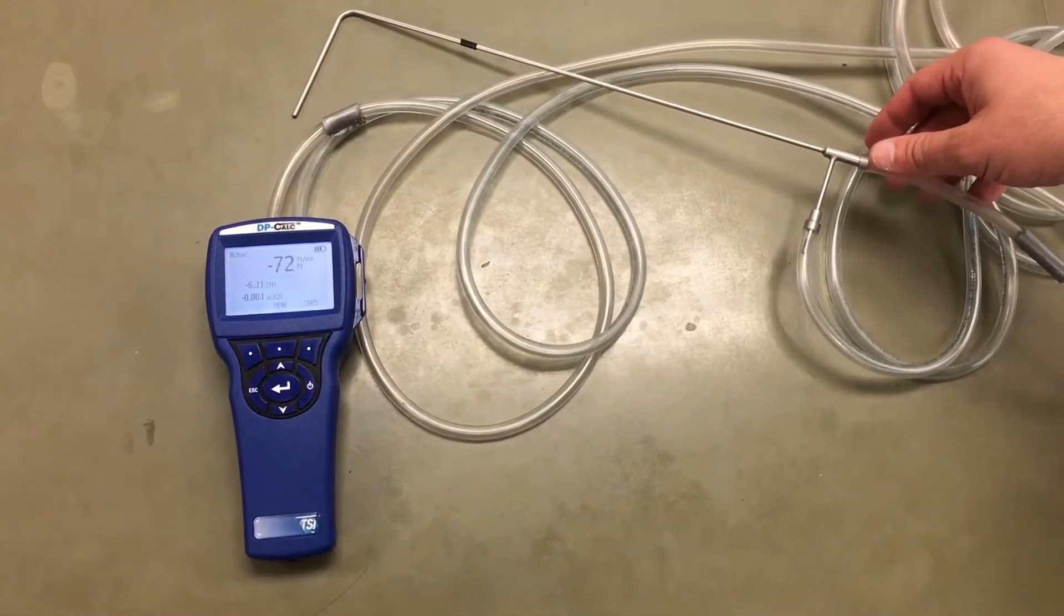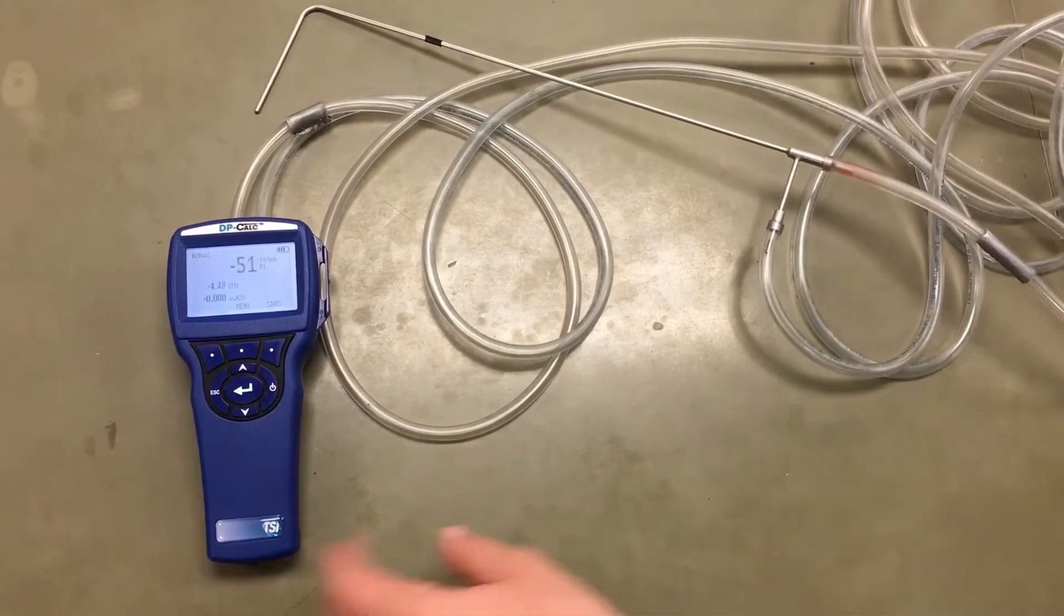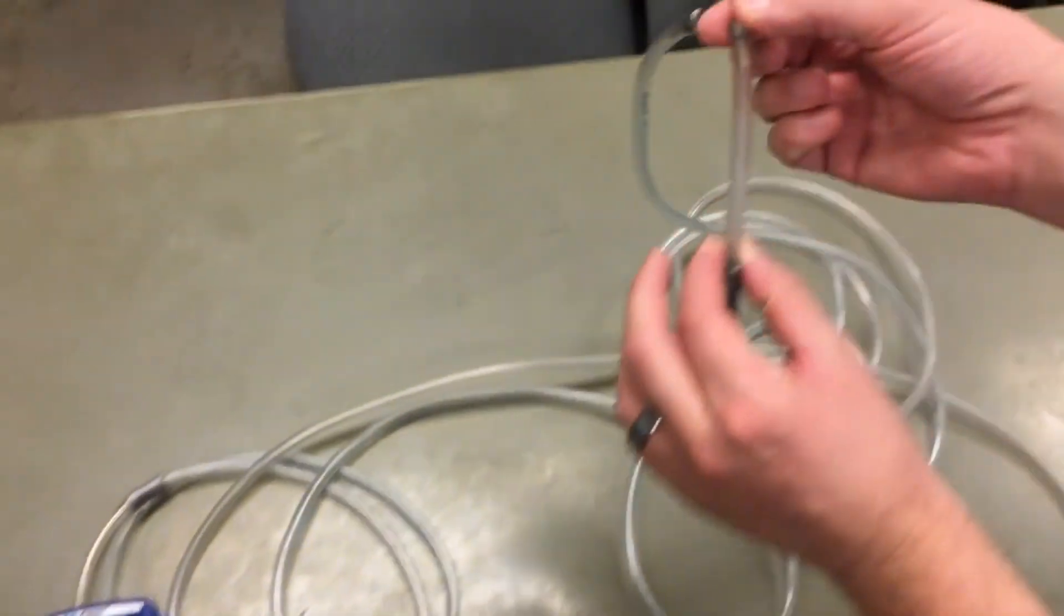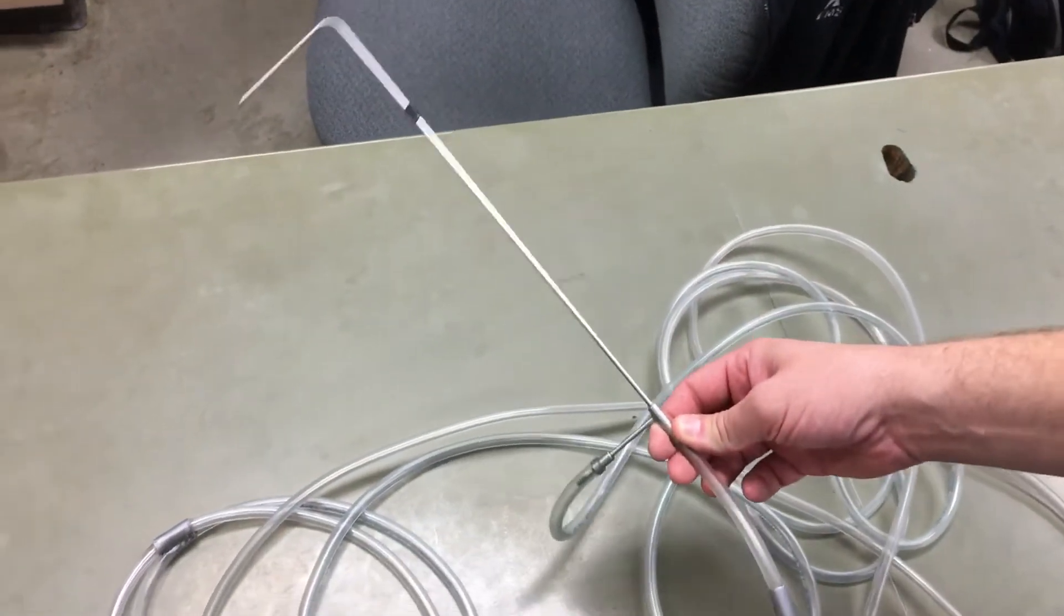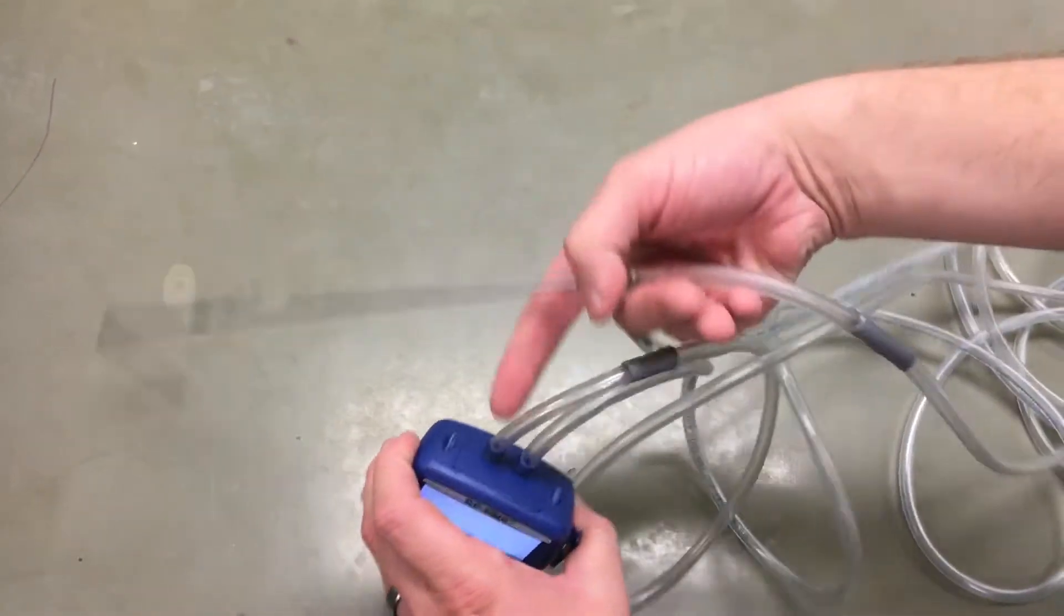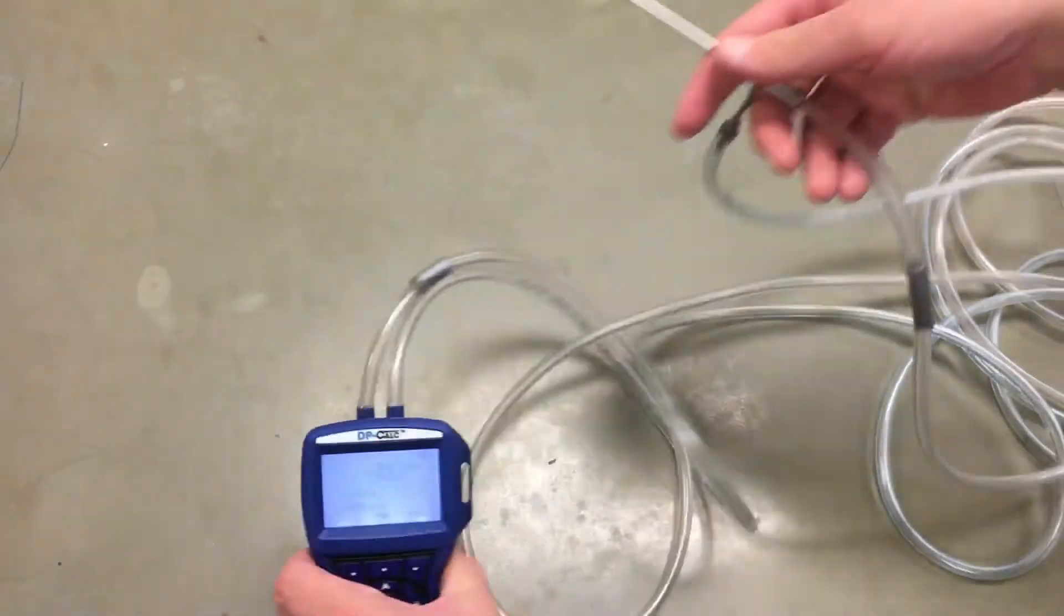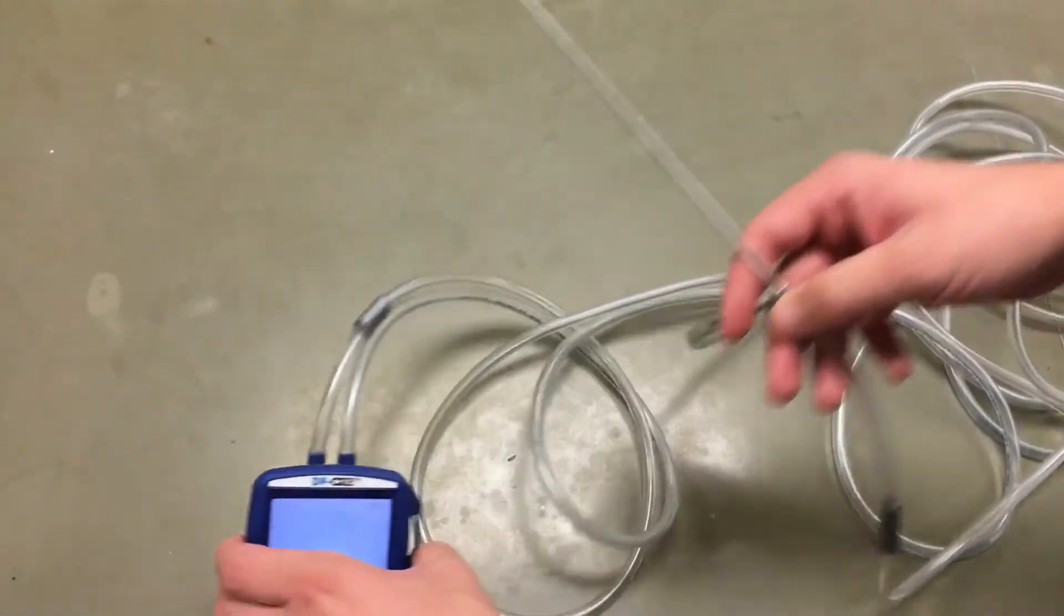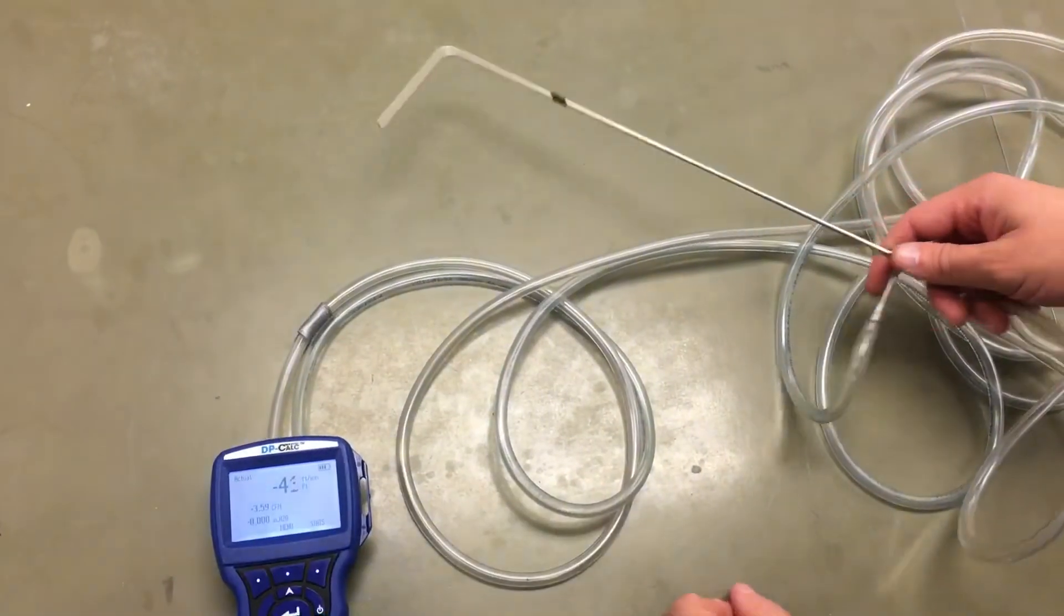We'll also measure the velocity pressure inside a ventilation duct. We've got our pitot tube hooked up, with the velocity pressure line hooked up to the positive port on the meter, and our static pressure line hooked up to the negative port on our meter.